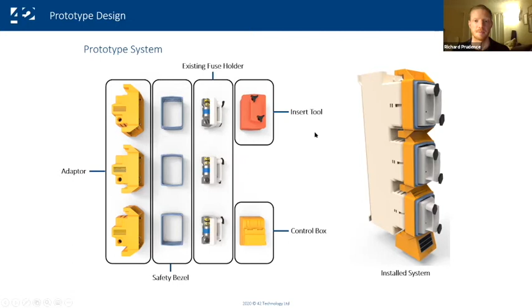When it comes to data logging, the good thing about FuseOhm as opposed to the maximum demand indicator or any Rogowski coil-based measurement is that we're able to measure voltage, and we can also infer the exact phase angle for each of the phases. As part of that, we get true power measurement.